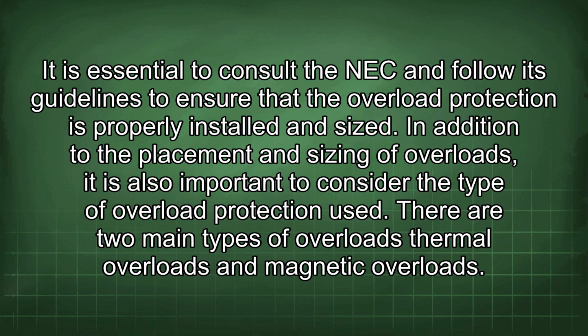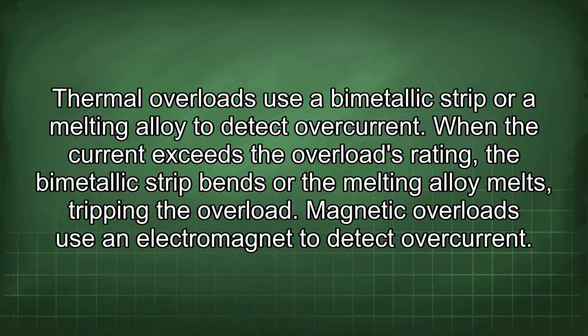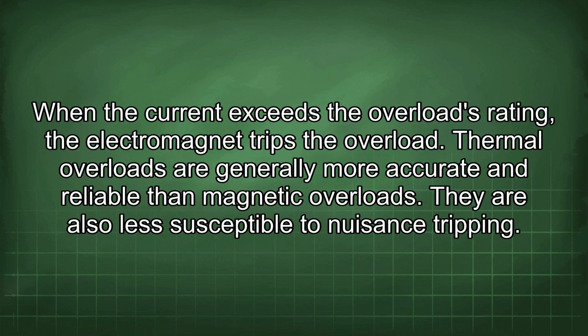In addition to the placement and sizing of overloads, it is also important to consider the type of overload protection used. There are two main types of overloads: thermal overloads and magnetic overloads. Thermal overloads use a bimetallic strip or a melting alloy to detect overcurrent. When the current exceeds the overload's rating, the bimetallic strip bends or the melting alloy melts, tripping the overload. Magnetic overloads use an electromagnet to detect overcurrent. When the current exceeds the overload's rating, the electromagnet trips the overload.